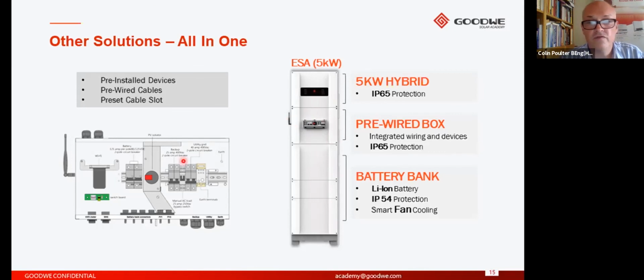protected, and the purpose of this box is to neatly house all of the cabling aspects and monitoring aspects of the wiring requirements. So on the left hand side here, you can see that within this box we have the Wi-Fi module. This set of breakers here is for providing a disconnect to the battery supply. This red switch here in the middle is the DC isolator from the PV. And on the right here, we have the breakers for both the on-grid side connection and the backup side breakers, and on the right hand side here is the on-grid breakers.